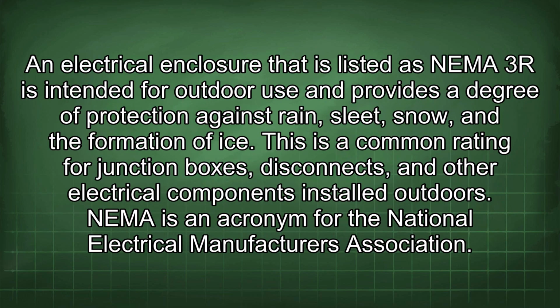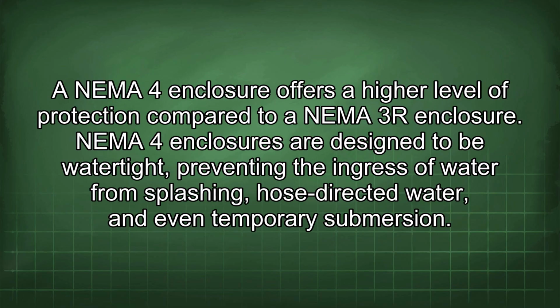An electrical enclosure that is listed as NEMA 3R is intended for outdoor use and provides a degree of protection against rain, sleet, snow, and the formation of ice. This is a common rating for junction boxes, disconnects, and other electrical components installed outdoors. NEMA is an acronym for the National Electrical Manufacturers Association. A NEMA 4 enclosure offers a higher level of protection compared to a NEMA 3R enclosure.